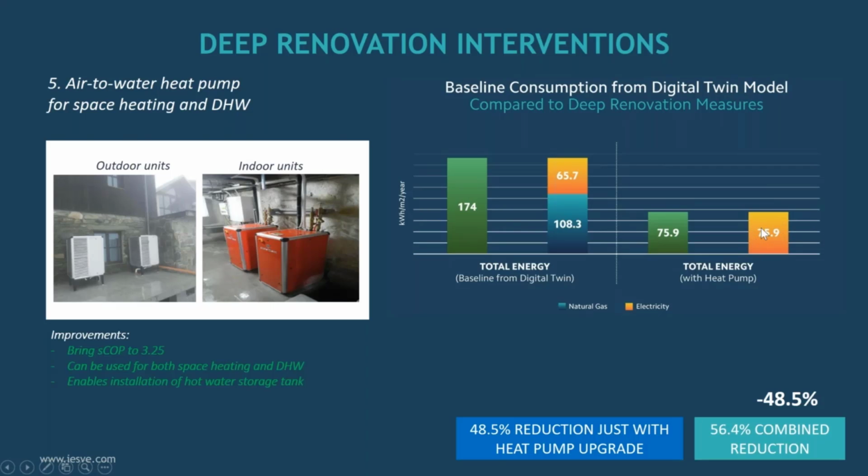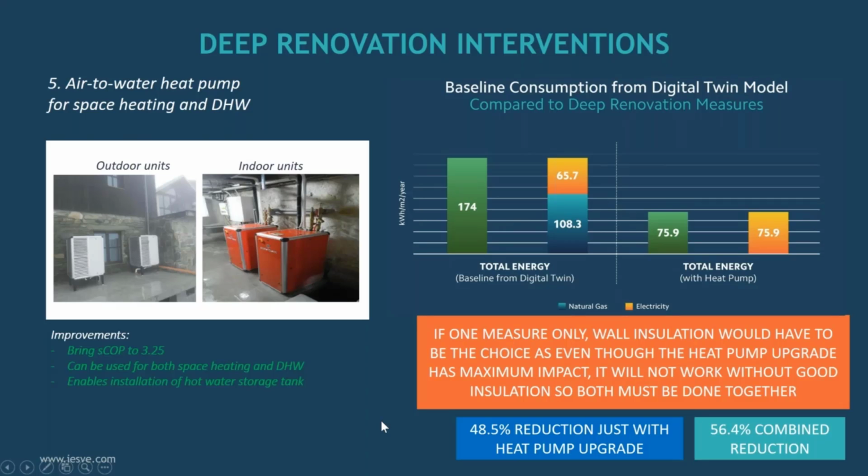And you can see that it's obviously higher than before because we are now heating the building through electricity, but we completely got rid of the natural gas consumption. So we have a huge saving of 48.5%.